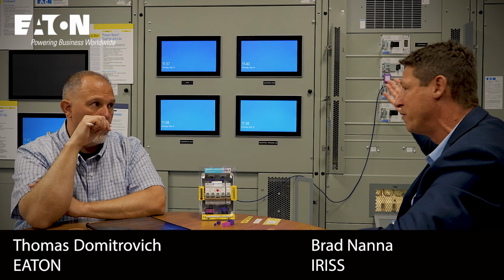So you can't just go to Tom's garage and put in a plexiglass. No, you can't. There's real thought in the glass material so the thermography can go through it. I didn't know that. There are two types. There's a crystal window that most companies use, and crystal is okay, but the problem is it's hygroscopic, it absorbs moisture, so it's not a matter of if but when it will fog up and you can no longer shoot thermography through it. You're not worried about shock hazard, just visibility.